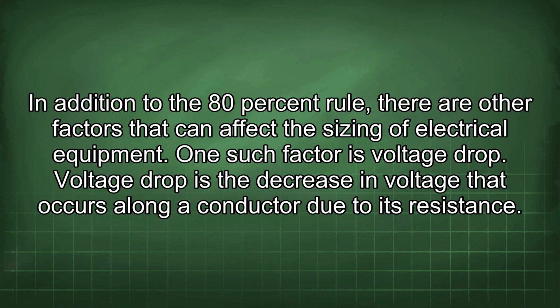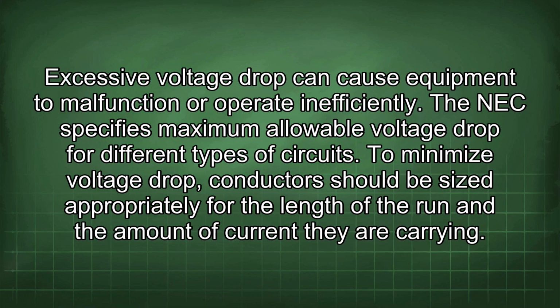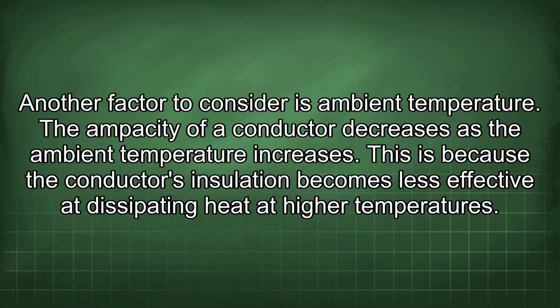In addition to the 80% rule, there are other factors that can affect the sizing of electrical equipment. One such factor is voltage drop. Voltage drop is the decrease in voltage that occurs along a conductor due to its resistance. Excessive voltage drop can cause equipment to malfunction or operate inefficiently. The NEC specifies maximum allowable voltage drop for different types of circuits. To minimize voltage drop, conductors should be sized appropriately for the length of the run and the amount of current they are carrying. Another factor to consider is ambient temperature.